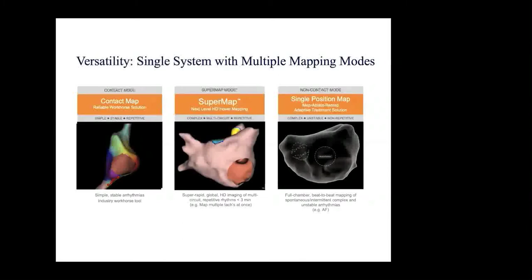During the super map, as you can see in the middle part of the slide, the operator is moving in the chamber with a basket catheter, and the system indicates for us if the mapping of a certain part is good enough. And then the operator can move further, and then at the end of the mapping, it provides us a color-coded propagation map. This is very fast, and this kind of mapping is very useful to map repetitive rhythms because the algorithm it is based on is specifically designed for repetitive rhythms.